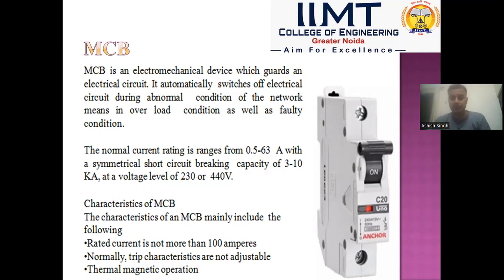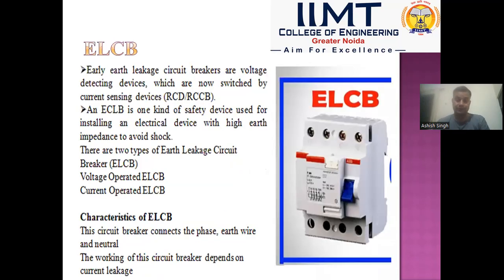And when our device is overloaded or overload current is flowing through MCB, then it operates using the thermal effect of current. For that purpose, we are using a bimetallic strip, and when the bimetallic strip heats, it gets bent down and the latch is on.